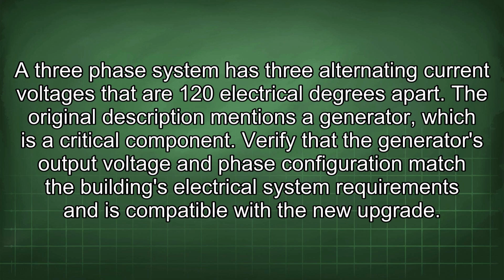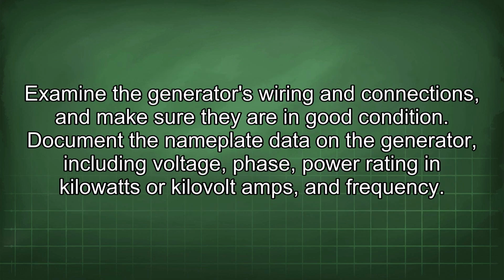The original description mentions a generator, which is a critical component. Verify that the generator's output voltage and phase configuration match the building's electrical system requirements and is compatible with the new upgrade. Examine the generator's wiring and connections and make sure they are in good condition. Document the nameplate data on the generator, including voltage, phase, power rating in kilowatts or kilovolt amps, and frequency.